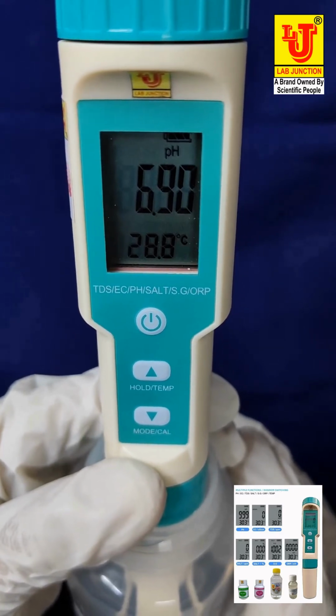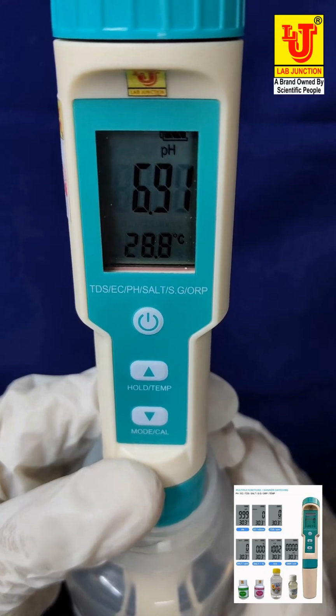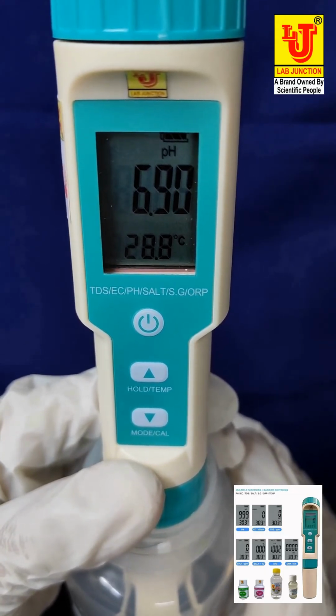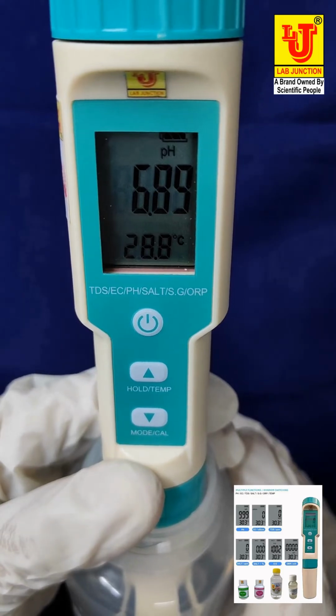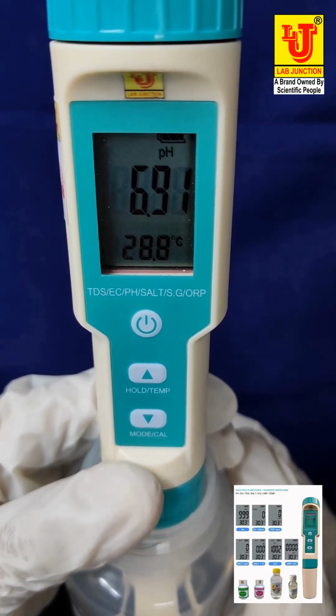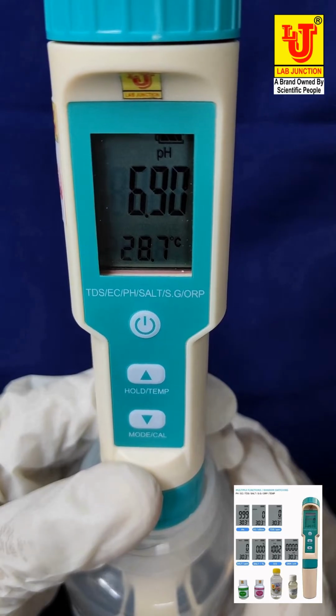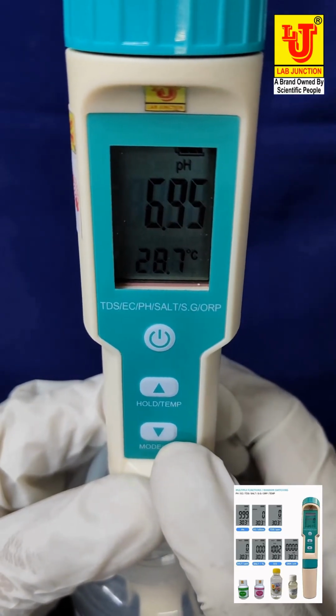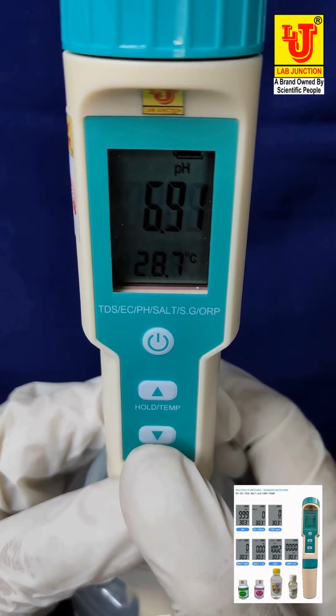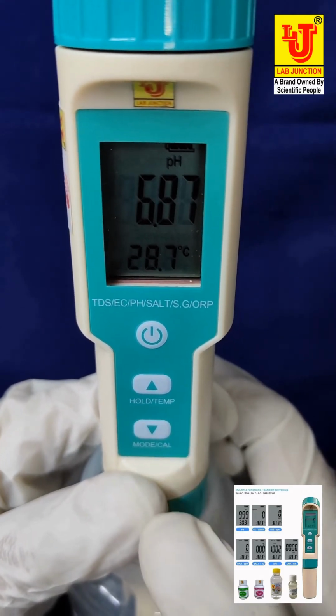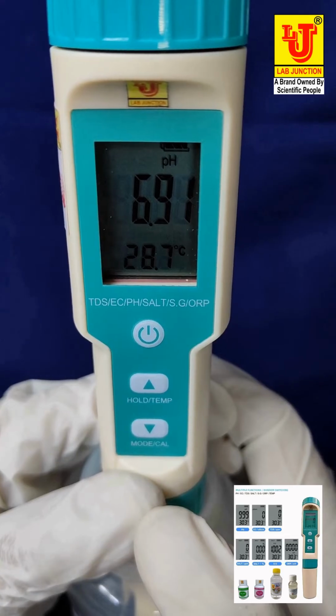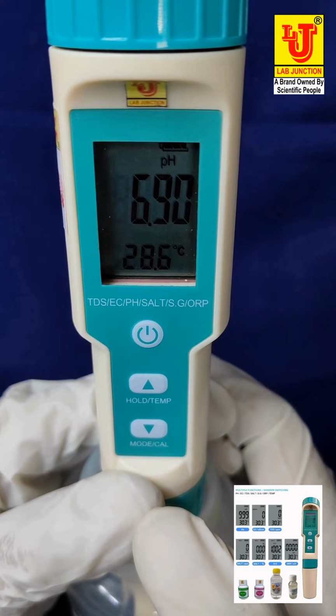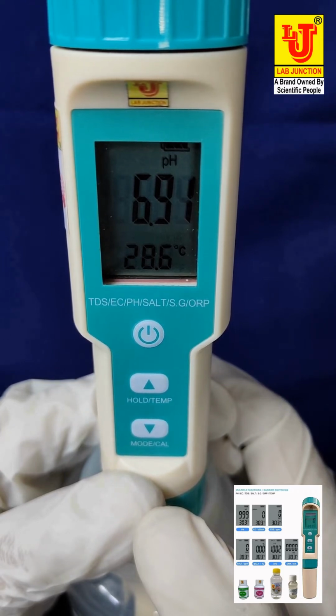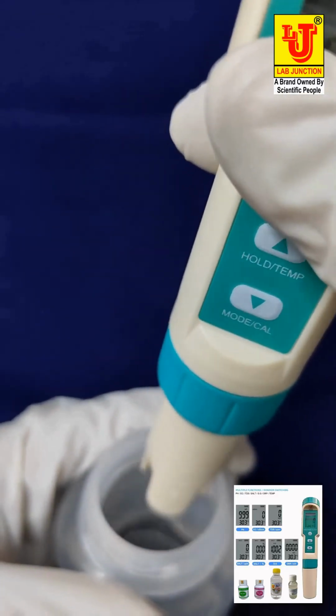Any parameter you want to calibrate, go to that parameter: pH, conductivity, TDS, ORP, SG, and press the cal key for 3 seconds and release that key. Automatically cal mode is active and calibrate with your standard solution like this. Now I am calibrating conductivity.